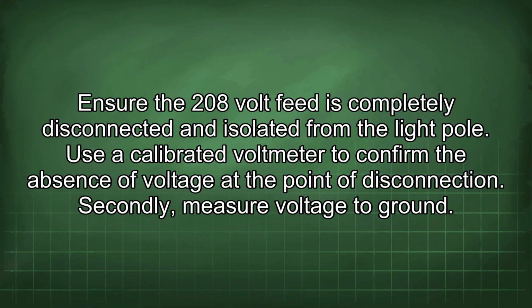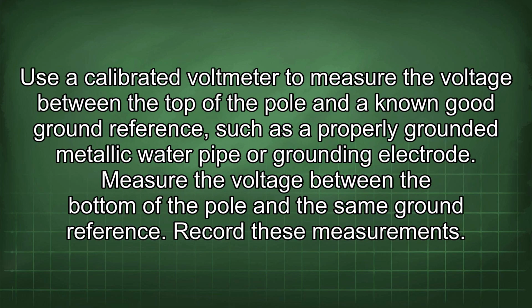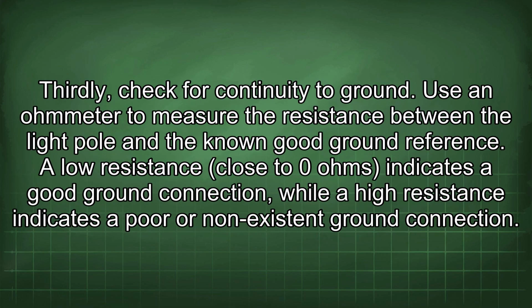Secondly, measure voltage to ground. Use a calibrated voltmeter to measure the voltage between the top of the pole and a known good ground reference, such as a properly grounded metallic water pipe or grounding electrode. Measure the voltage between the bottom of the pole and the same ground reference. Record these measurements.